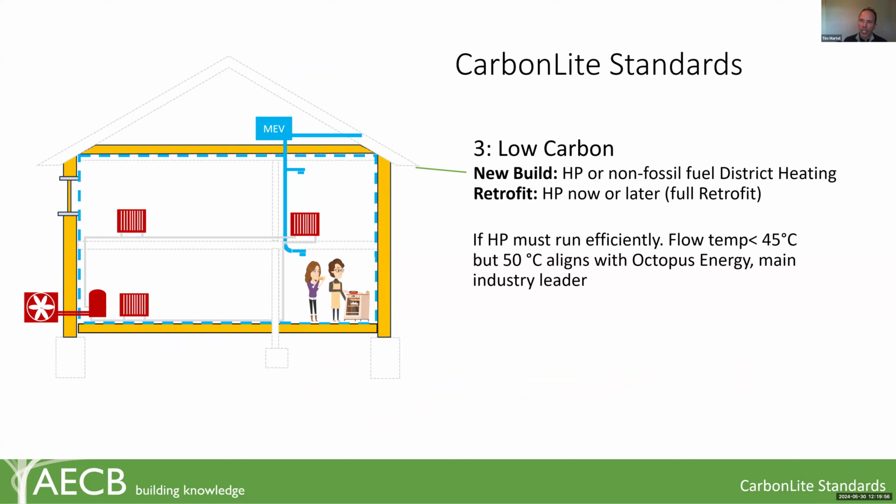And as I was saying, the heat pump must be installed efficiently, flow temperature less than 45 degrees, but 50 degrees aligns with Octopus Energy, so we allow that too.